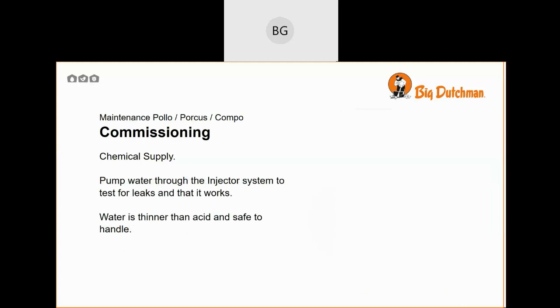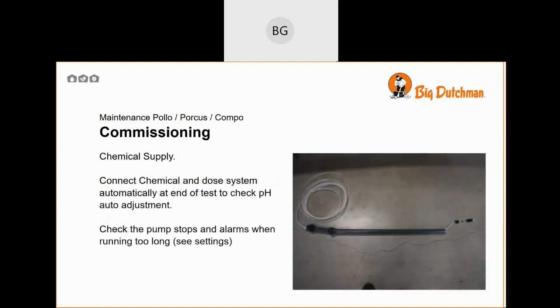Pump water through the injector system to test for leaks and that it works. Water is thinner than acid and safe to handle. This means it will expose any leaks, and if there are any leaks, it won't be dangerous to handle them. Connect the chemical supply and dose the system automatically at the end of the test to check the pH auto adjustment. Check the pump stops and alarms when running too long. See the settings.